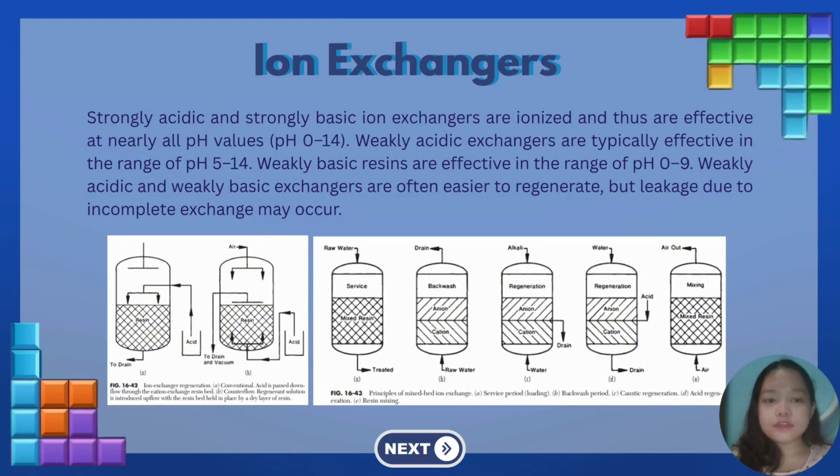In Figure 16-42, regeneration methods. Regeneration is the process of restoring ion exchangers to their original ionic form. In conventional regeneration, Figure 16-42A, acid is introduced at the top and flows down through the resin bed. In Figure 16-42B, counterflow regeneration, the acid is introduced from the bottom and pushes upward, which is more effective because it minimizes resin mixing and improves contact.